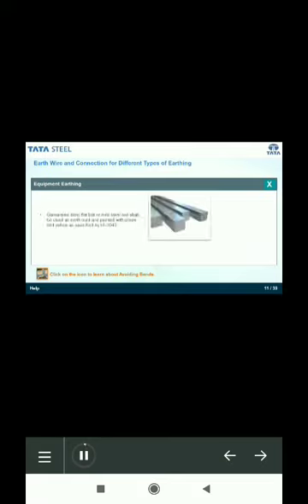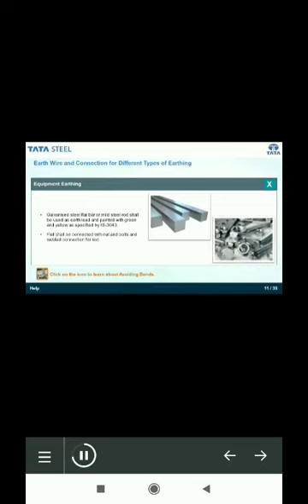For equipment earthing, galvanized steel flat bar or mild steel rod shall be used as earth lead and painted with green or yellow as specified by IS 3043. Flat shall be connected with nut and bolts and welded connection for rod.